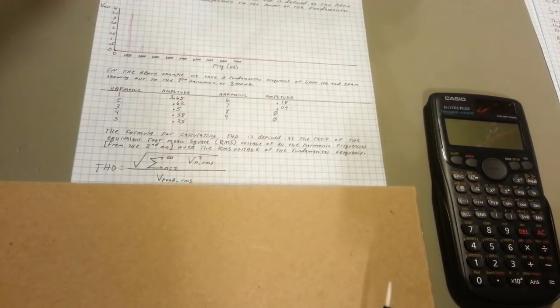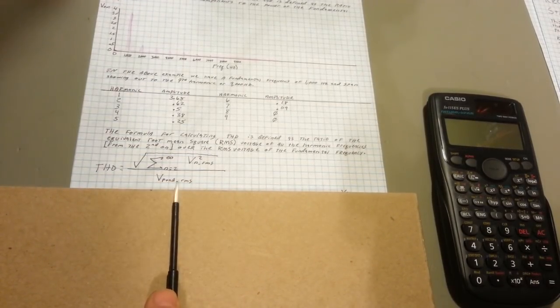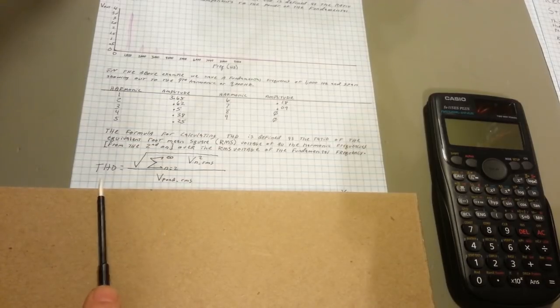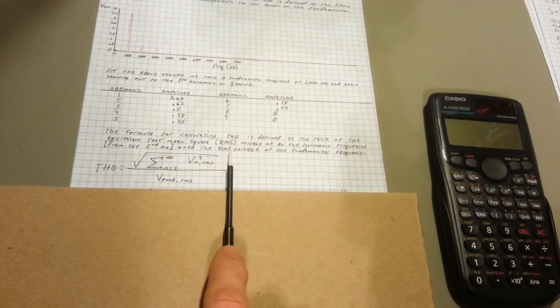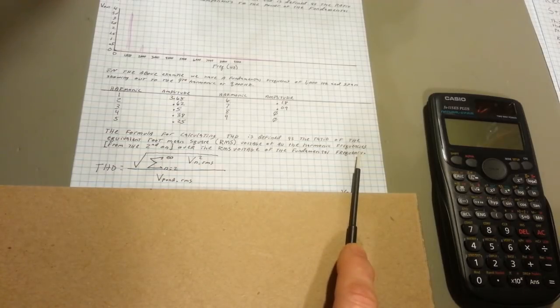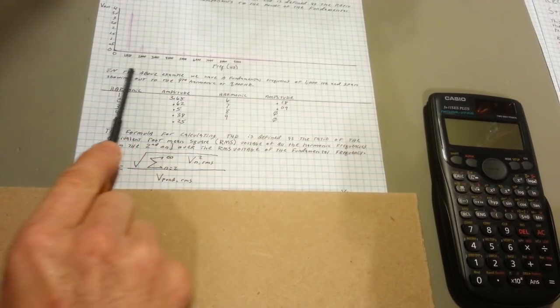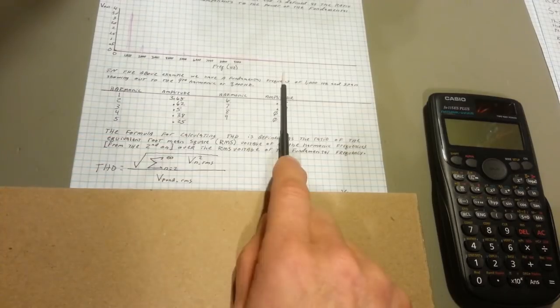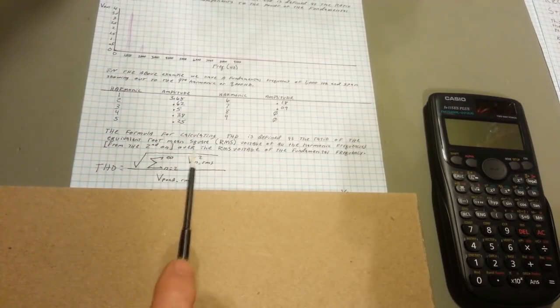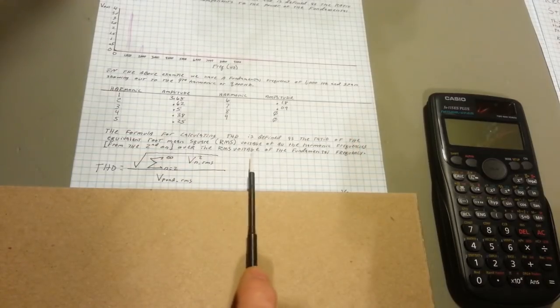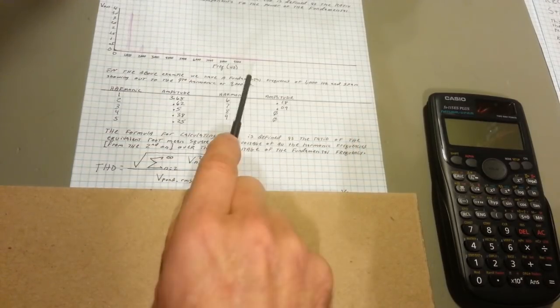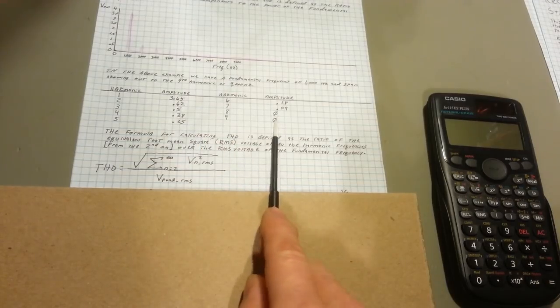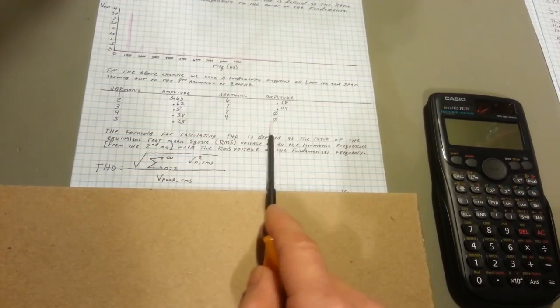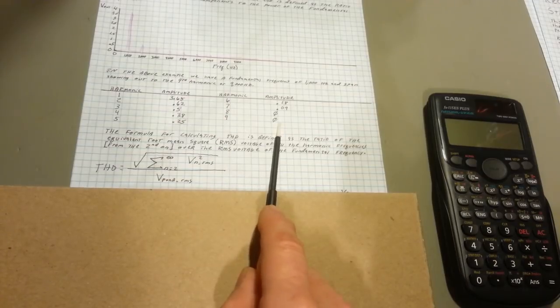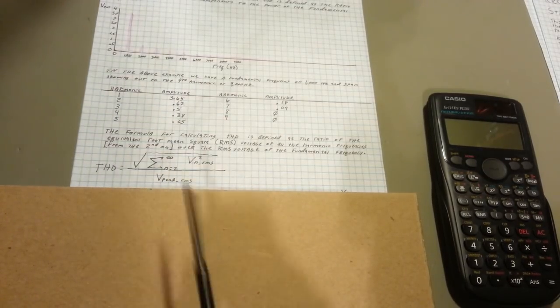The formula for calculating THD is defined as the ratio of the equivalent root mean square, RMS, voltage of all the harmonic frequencies from the second harmonic on, basically to infinity, over the RMS voltage of the fundamental frequency. Like I said, we're only measuring out to the ninth harmonic because, as you can see here, there's nothing measurable even past the seventh harmonic. But mathematically on this formula, and don't let formulas like this scare you.